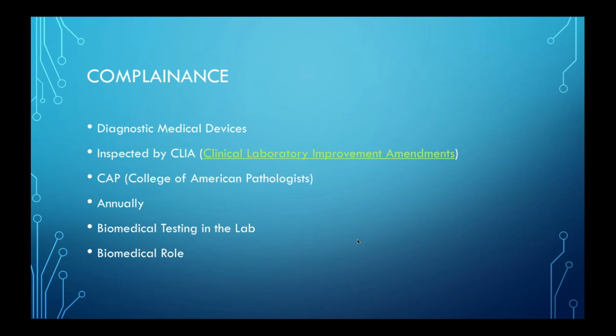The techs, the medical technicians that do the testing, are very familiar with their medical devices. So when they call to have something repaired, I can assure you they've already done all the basic troubleshooting that they can. And there's probably a serious problem with the unit that would need to be done either by the field service technician on site or the biomed, if the biomed is trained on that.